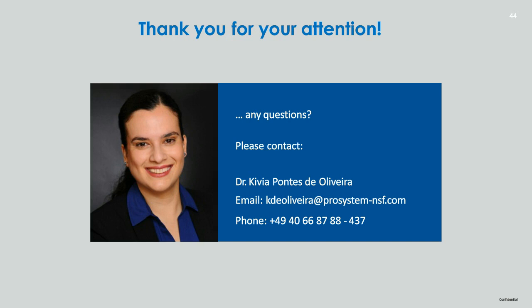Okay, thank you. Question here asking, what does state-of-the-art mean? State-of-the-art in Europe means what most people are currently using. It does not necessarily mean that it is the newest technology, because sometimes it is not clear whether this new technology is the safest one. You should think about it as a risk-benefit analysis and its relationship with other medical alternatives. A new technology may slightly improve performance, but its risks may be higher than the ones from another technology that has been already long in the market and has been routinely used in hospitals and clinics.